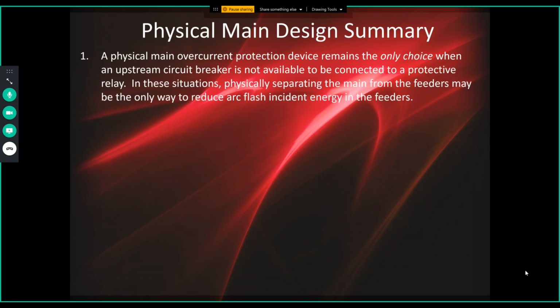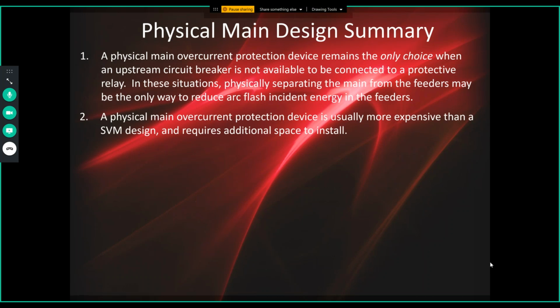So in terms of physical main design summary, we readily acknowledge that if the utility owns the transformer, a secondary virtual main is not possible. In these situations, separating the secondary main from the feeders is probably your best solution. Because secondary virtual mains become so much more popular and make so much sense, we've seen many owners who previously accepted secondary metering now move to a primary metering solution where they own the transformer, so they take the lower electrical rate that's offered by the utility that pays for the transformer. They own the transformer. Now they can control the primary and have both a safe and maintainable secondary distribution solution.